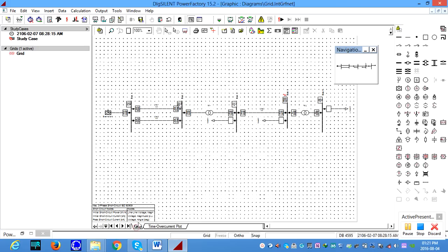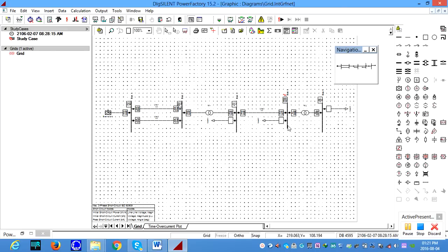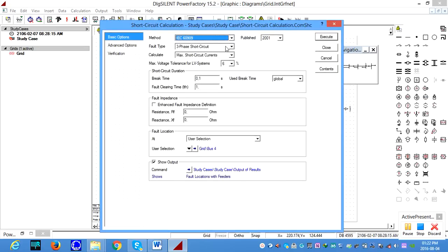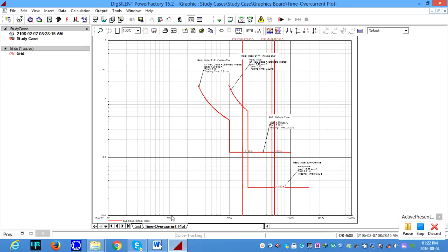Okay, we are happy. Now we need to apply a different fault, let's say a line to ground fault on the same bus. Calculate short circuit. We select single line to ground fault, execute and validate the tripping characteristics. We can see the ground elements are tripping now, at 0.2 seconds and also 0.30 seconds. It is a phase to ground fault, so the phase element is also tripping and the ground element, but according to the current magnitude, we need to know which phase element and ground element are tripping.